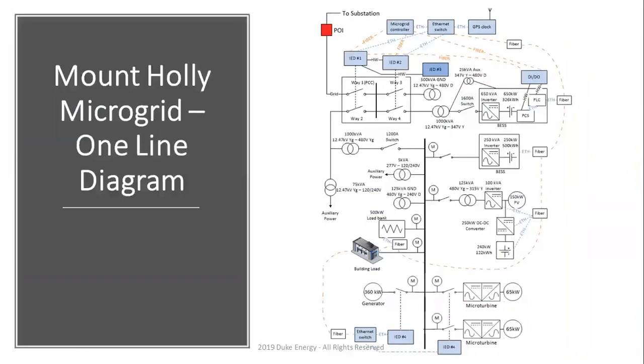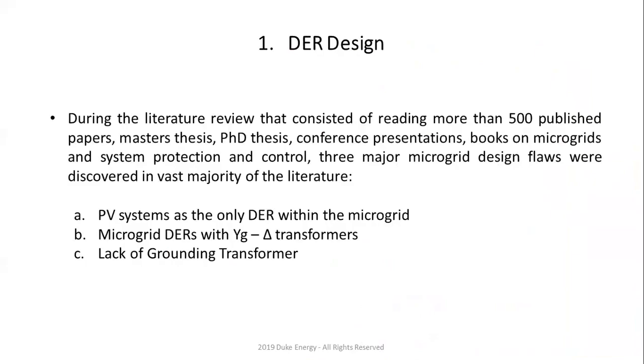On this particular picture, you can see 2 IEDs, which are pretty much relays. Recently, we have changed this, so now, rather than having 2 relays, we have 1 relay that controls everything. There's a grounding transformer with relay number 3. There's an AC coupled battery, and you can see out of way 2, we go through the transformer to create the 480 volt bus. That's where we have a DC coupled battery, micro turbines, generator. We had a second battery energy storage system that we have since removed, and we're looking for something else to put in there. You also have a communications diagram over here. You can see the microgrid controller, Ethernet switches, clocks, and how everything is connected.